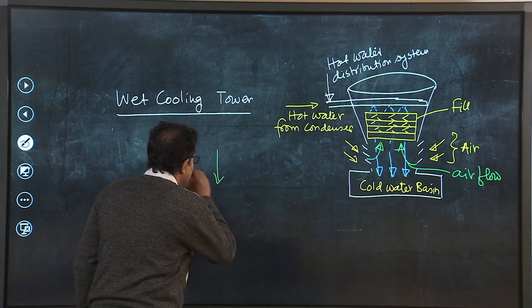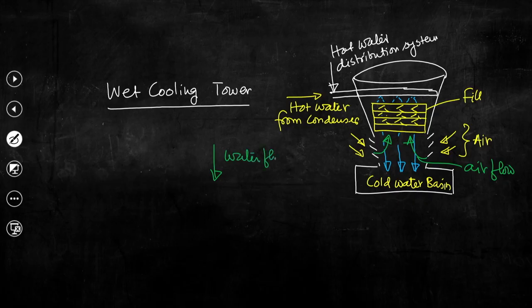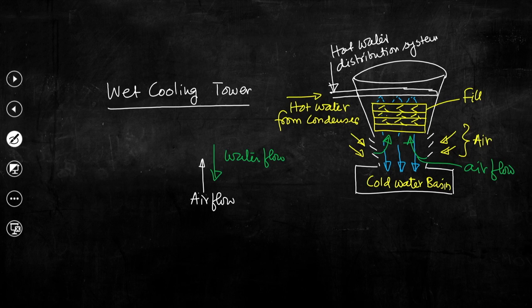Water is coming down and air is going up — this is a counter flow type arrangement. When these two streams mix together, heat and mass transfer takes place. Basically the air which is at ambient temperature will take heat from the water coming down from the top fill to the bottom fill. Heat transfer will take place as well as mass transfer, because when ultimately we get the air from the top of the tower, that air is hot and moist.